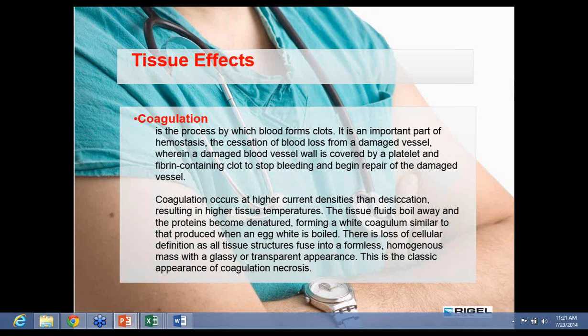So now I'm going to sum up these differences, okay? ESU modes and surgical objectives. When we're testing during our PMs, we have to test the ESU in monopolar and bipolar, cut and coag, and several different modes. Those different modes are also the same words that surgeons use, okay? So surgeons have categorized ESU modes by the changes to the structure of the cells. When we're doing a PM, we don't see any cell structure changing. But you have to remember that the key difference when you're talking to a surgeon or a nurse is that they're looking at desiccation and coagulation from the point of how it changes cell structure. They also talk about the type of cut the different waveforms produce. So they're interested in either fulguration or vaporization.